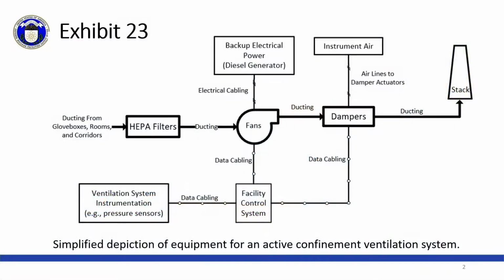The purpose of an active confinement ventilation system is to ensure that nearly all airborne radioactive particles are captured before the air is released outside. Exhibit 23 shows a simple diagram of an active confinement ventilation system with fans in the center that draw the facility air through high-efficiency particulate air filters, or HEPA filters, at the left to capture radioactive particles. The fans then expel the filtered air up the stack at the far right. Other systems needed to power and control the system are shown in the diagram as well.